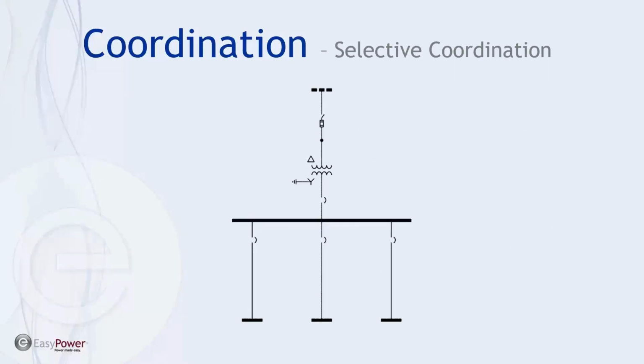Here's our one-line diagram, and we're considering selective coordination for loads that are going to be at the end of these feeders. If we have a remote fault, let's say I have a fault on this particular bus or load, that fault current is going to be sensed or felt by 3 different protective devices. The primary fusing in the transformer, the main breaker to this distribution panel or switchgear, and then the feeder breaker that's closest to the load.